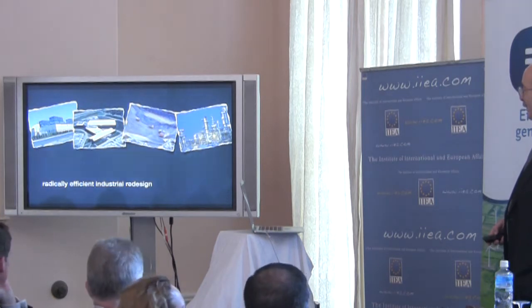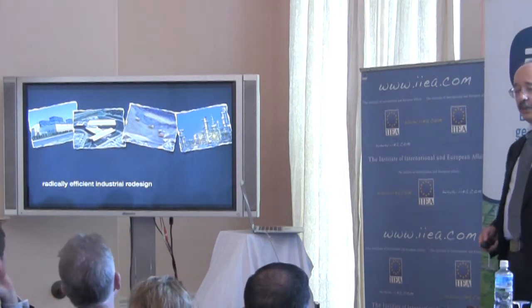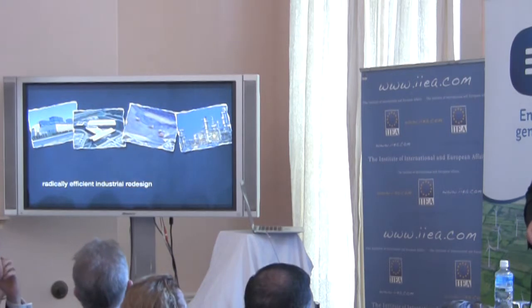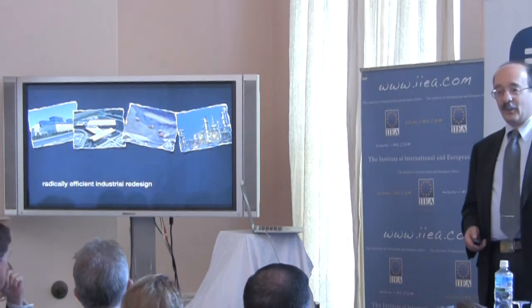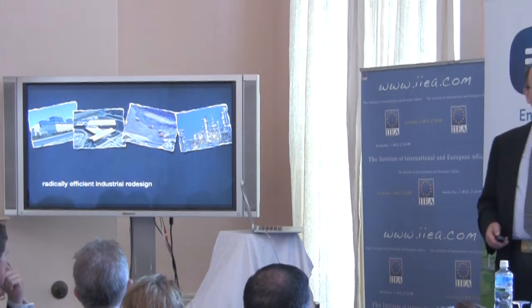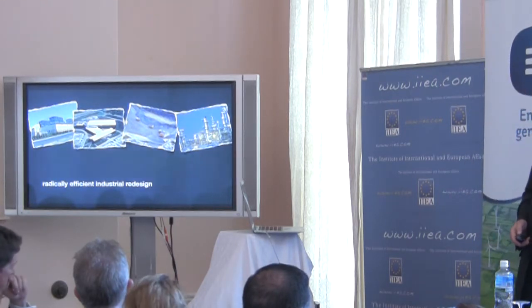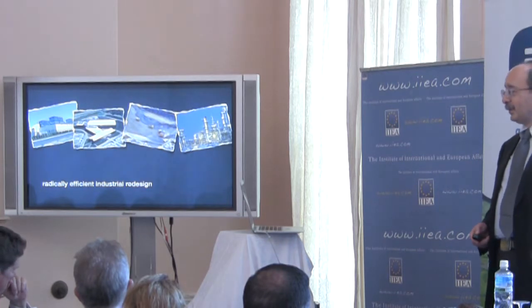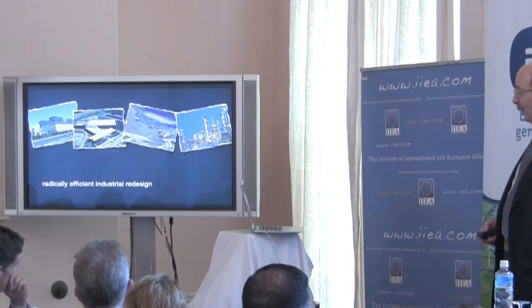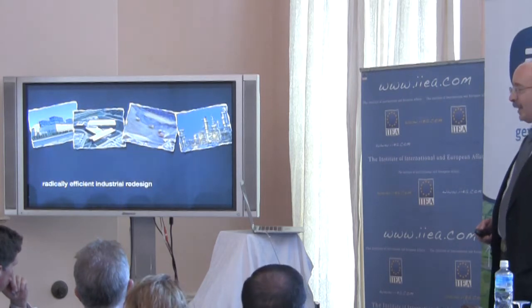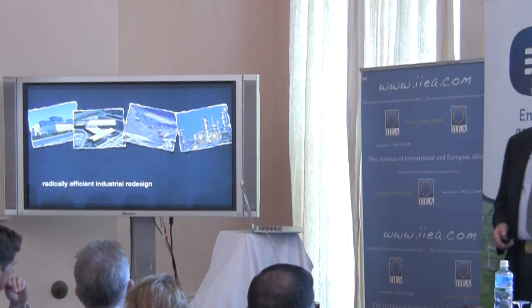The client for the data center in the north of England was the Inland Revenue, which wouldn't allow what was then EDS to adopt most of our recommendations. So we were able to triple the efficiency at the same cost, but EDS told us that had they been allowed to adopt all of our recommendations, which they considered sound, they would have saved about 95% of the energy and half the capex.